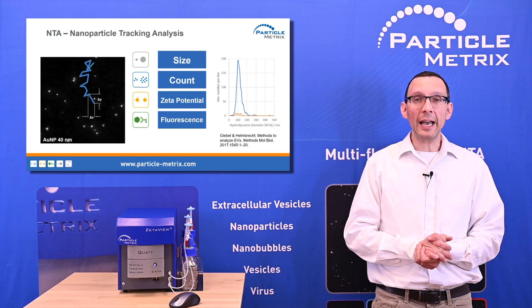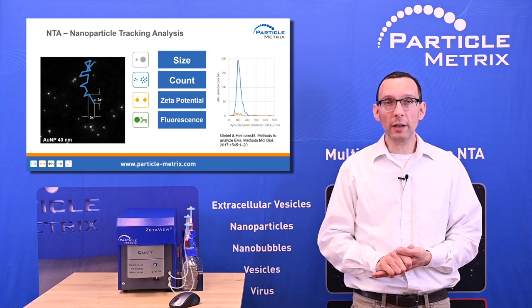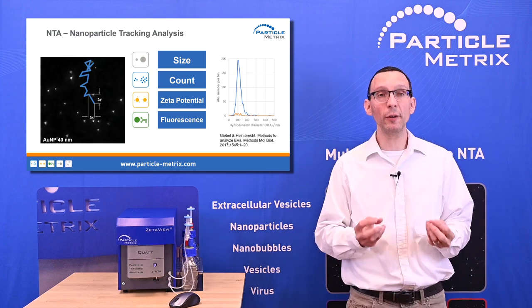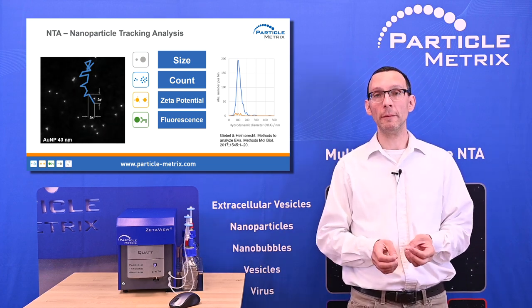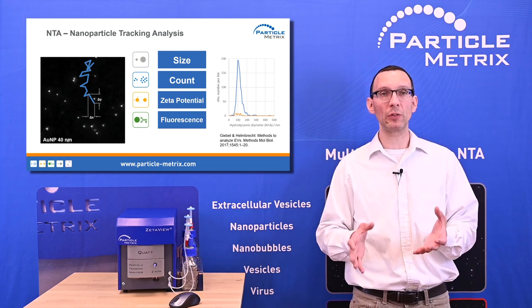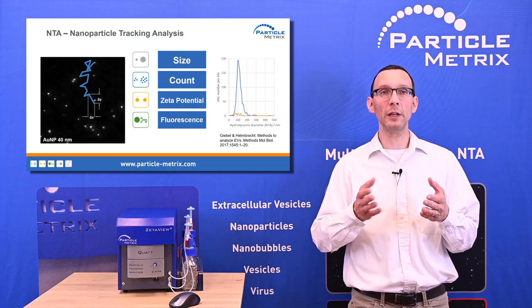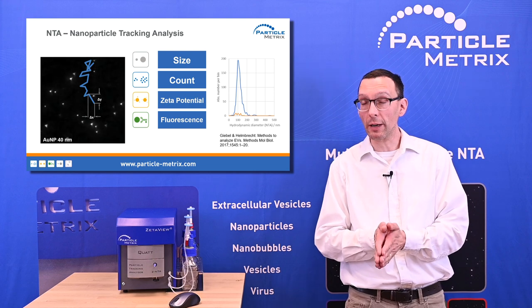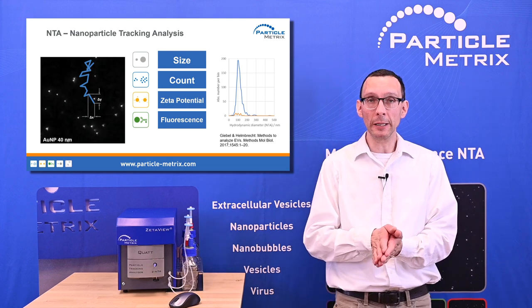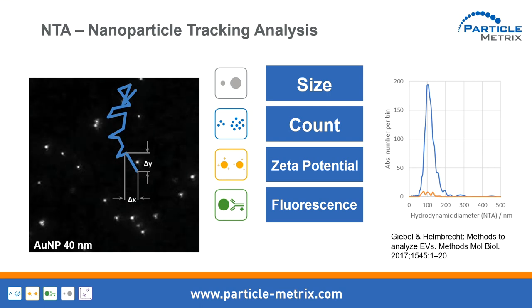We then added the feature of fluorescence detection, which is very important for obtaining specific information. With the help of fluorescent probes, we can detect fluorescence and distinguish between different types of particles by blocking the excitation light of the laser by means of a filter.